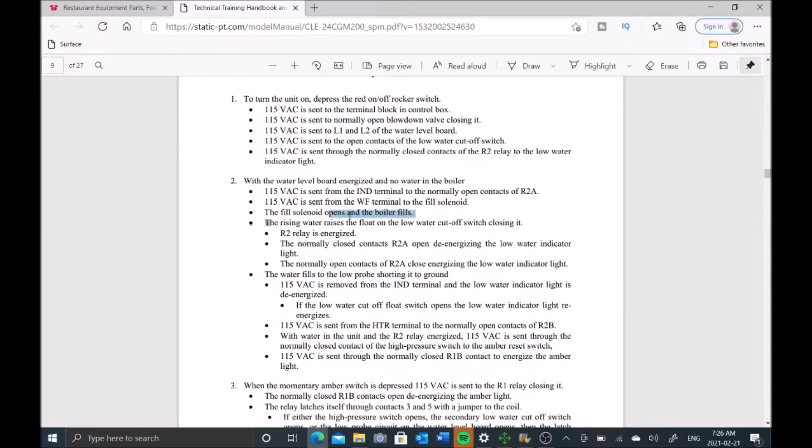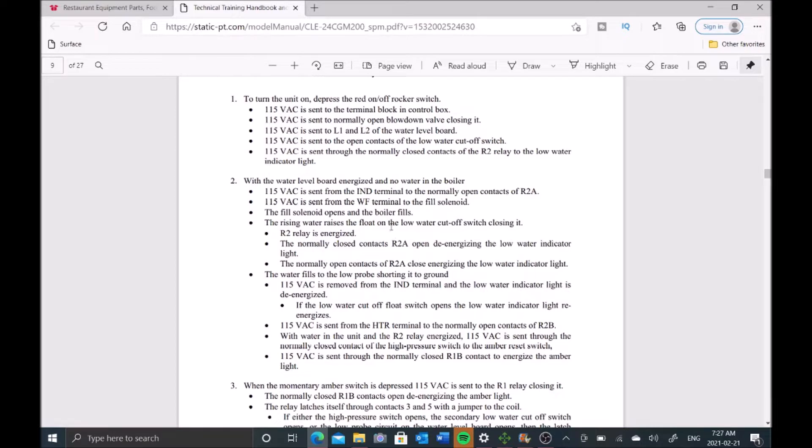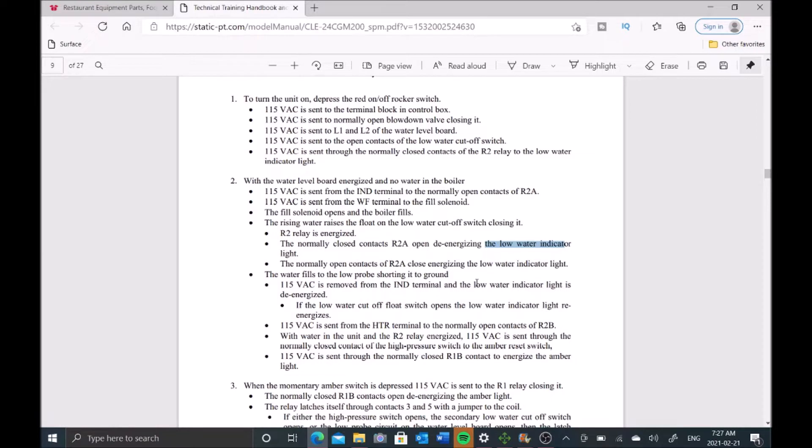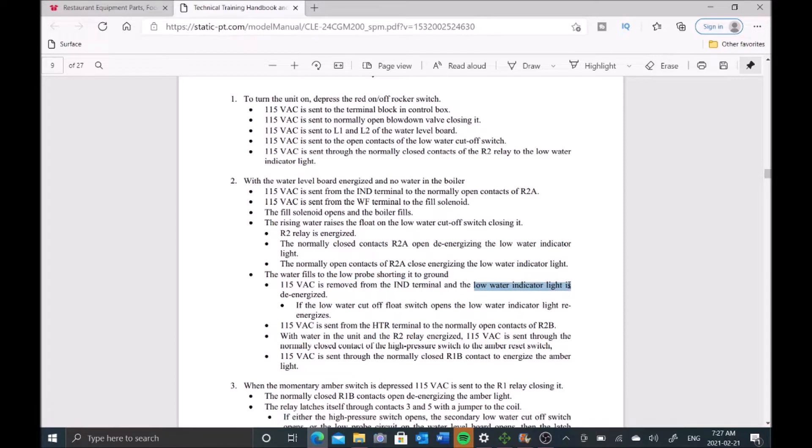The fill solenoid opens and fills the boiler. The rising water raises the float on the low water cutoff switch, closing it. Once that happens, this low water indicator light should go off. The water fills to the low probe, shorting it to ground, and that should also remove the low water light.